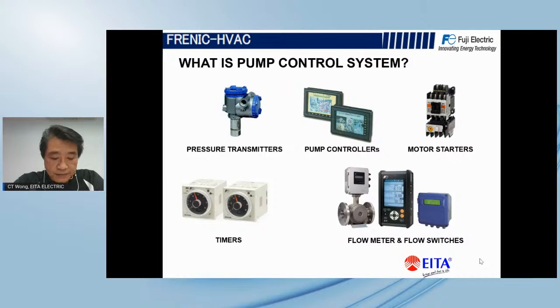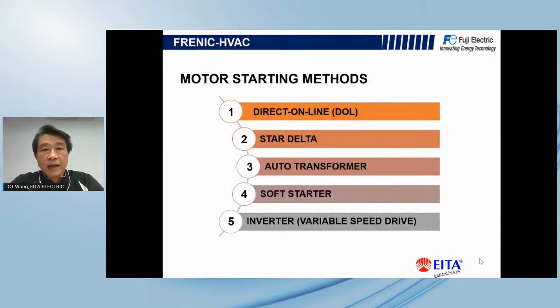What is the pump control system? A pump control system or pump controller provides a full range of functions for single and multi-pump systems. The functions include components such as pump controllers, timers, start-stop by motor starters, protection devices, and also measuring instruments such as flow meters, pressure switches or pressure transmitters. All of these are basically the components we use in the pump control system.